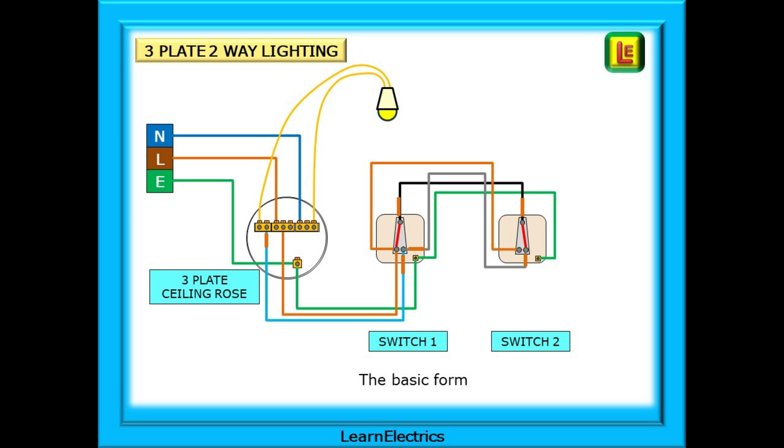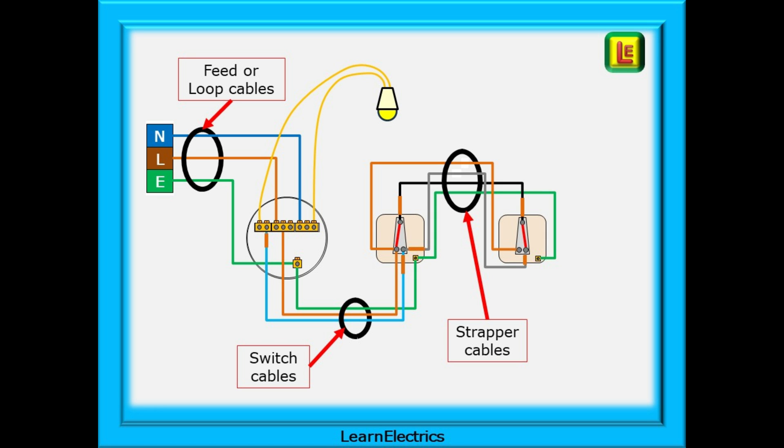This is a basic two-way lighting circuit with a three plate ceiling rose. We've laid it out this way so that it is easier to follow which parts of the circuit are actually under test at any one time. For most domestic installations the conductors will be installed as part of a grey sheathed cable. The feed cable or loop cable as it is sometimes called is often 1.5 square millimeter twin and earth. The switch cables will be the same but some electricians will use one millimeter twin and earth cable here and then the three core plus earth strapper cable for the two-way switching.